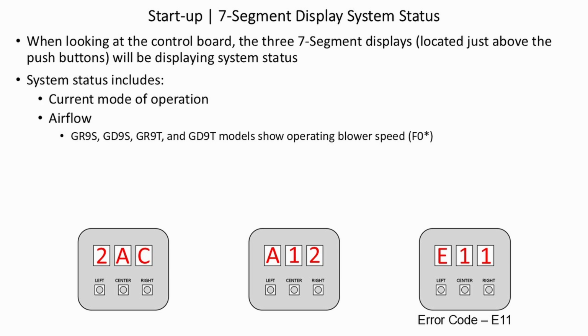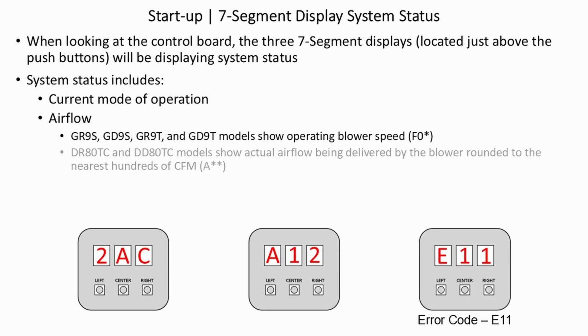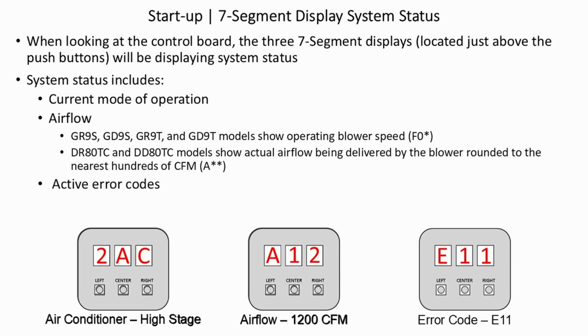GR9S, GD9S, GR9T, and GD9T models will show operating blower speed, F0 for instance. DR80TC and DD80TC models will show the actual airflow being delivered by the blower rounded up to the nearest 100 CFM, again as shown in the center example below. Active error codes, as shown in the example below on the right, E11, error code E11.